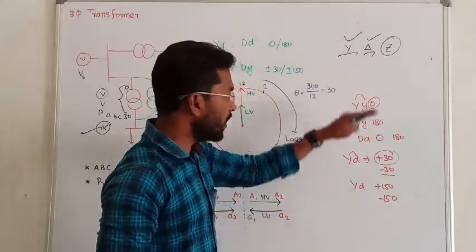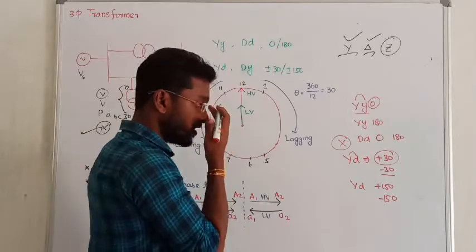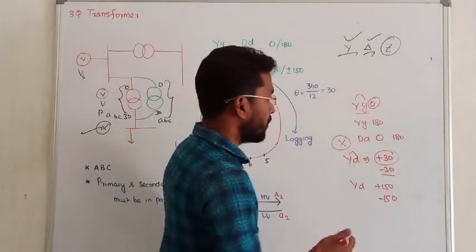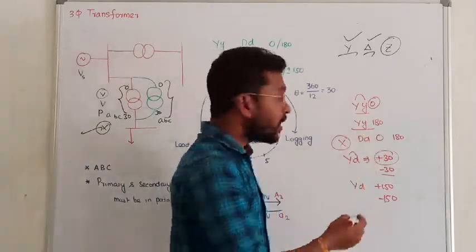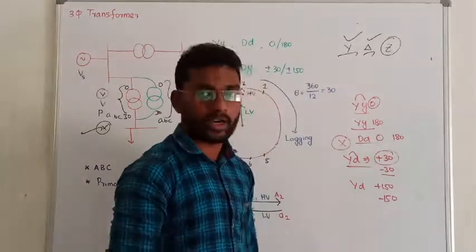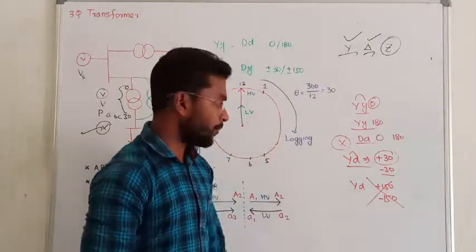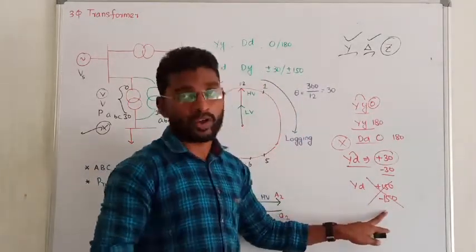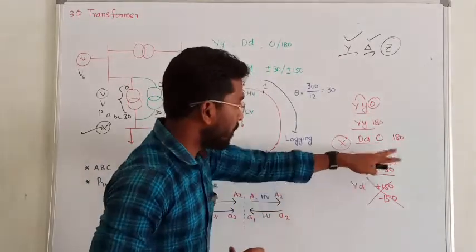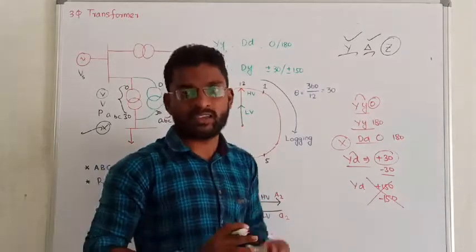So these are all the eight major combinations. To summarize: star-star at 0° and 180°, delta-delta at 0° and 180°, star-delta at +30° and −30°. The remaining delta-star combinations at ±30° are not going to be covered here — they are not that important. You can refer to J.P. Gupta's Power System for those.